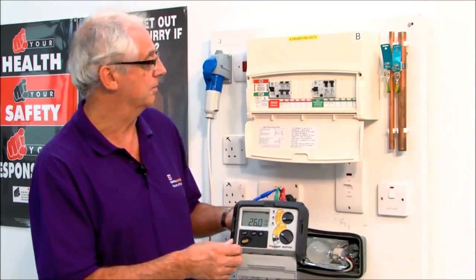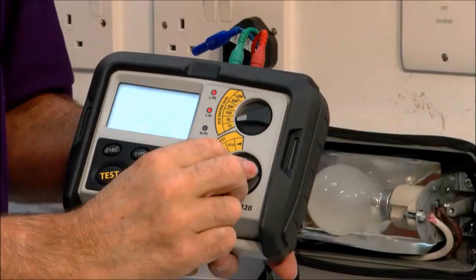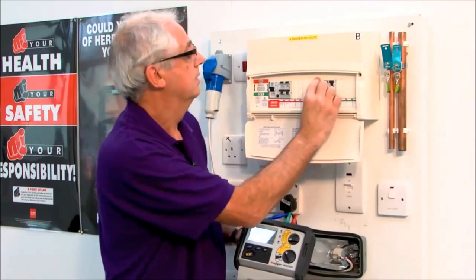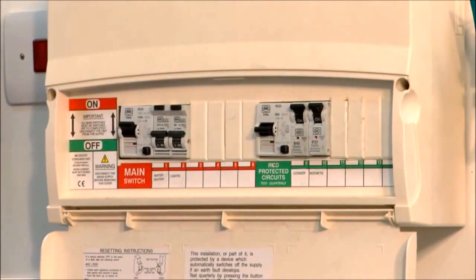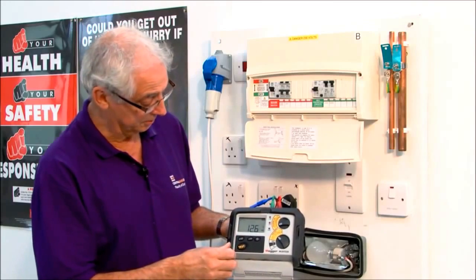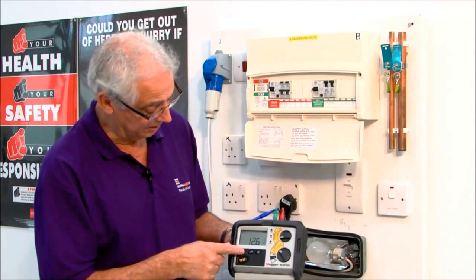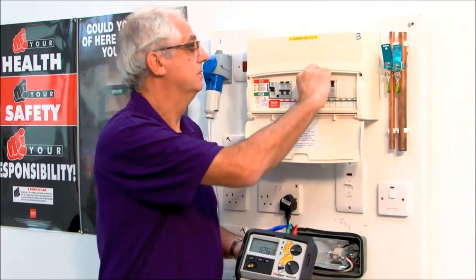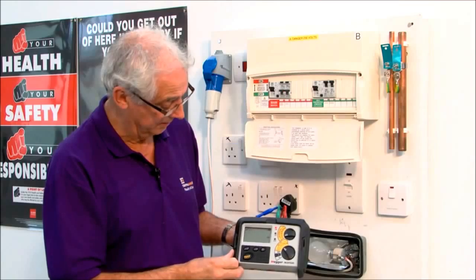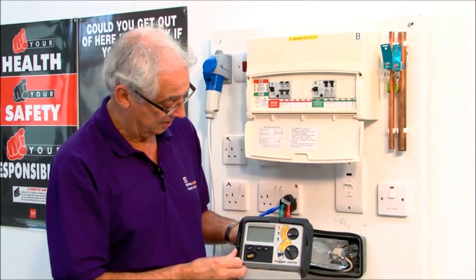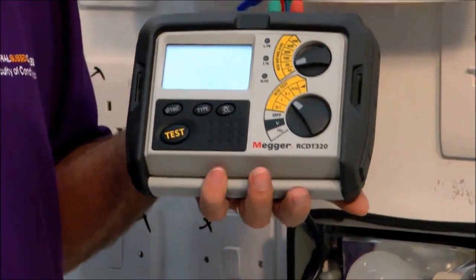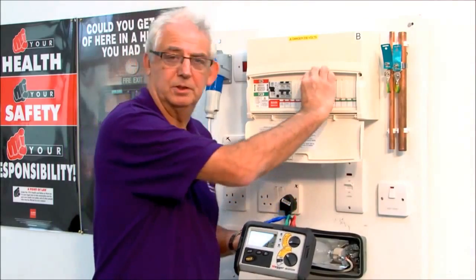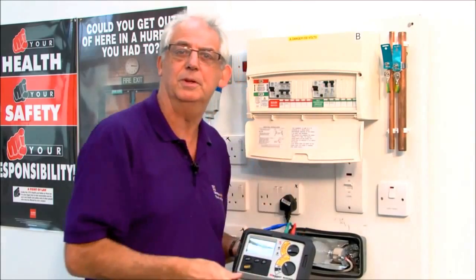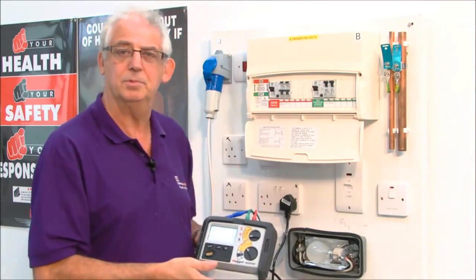As I say, 200 is the maximum. I now set this to times 5, turn it back on, push the button, 12.6 milliseconds. Need to do it at 180 degrees, turn it back on, push the button, and it's tripped within 6.8 milliseconds. So that's very fast, because on times 5 it should trip within 40 milliseconds. So this RCD is perfectly okay. Everything's working as it should be.